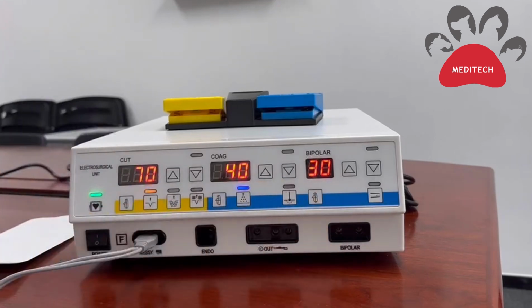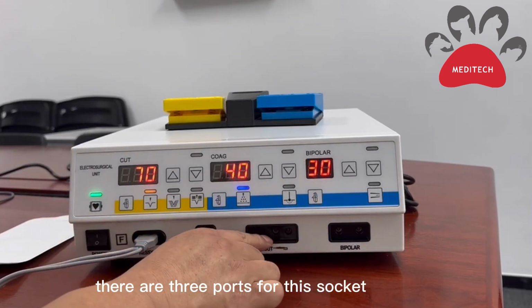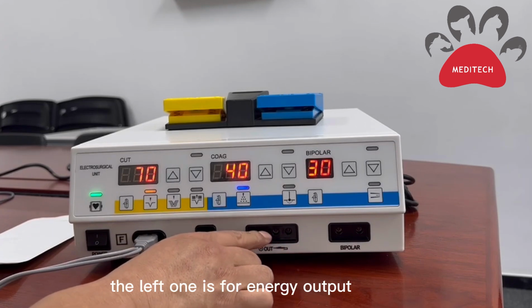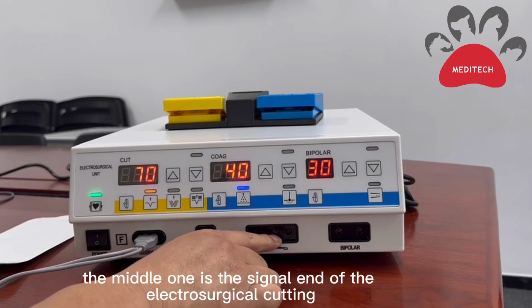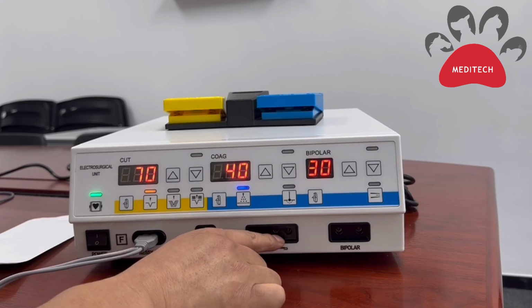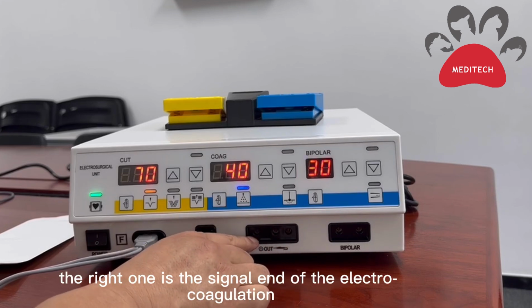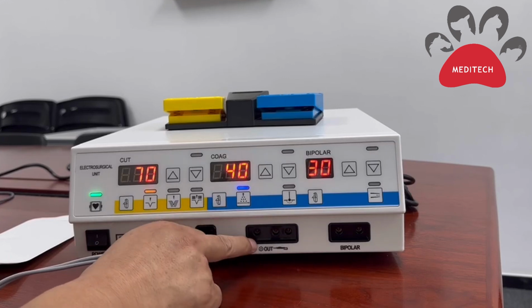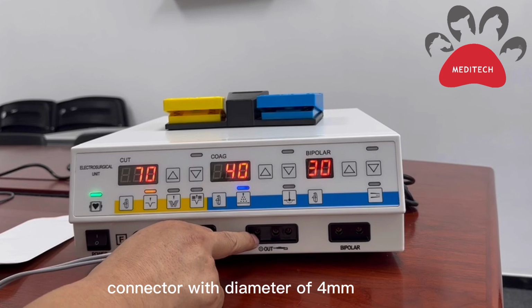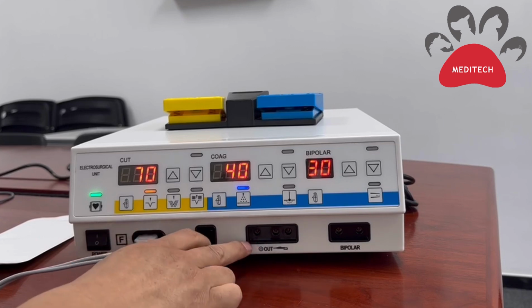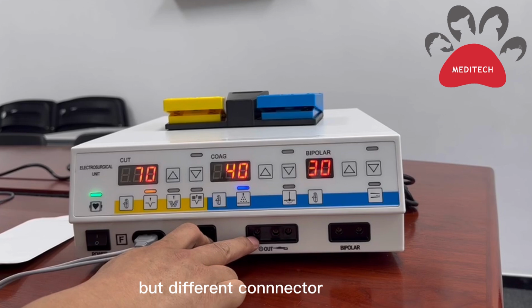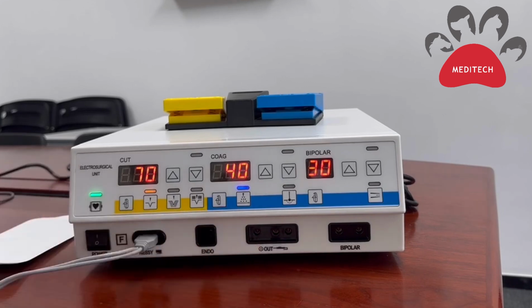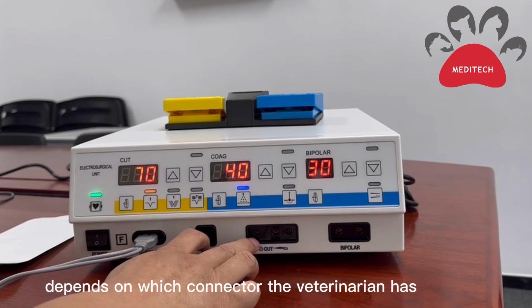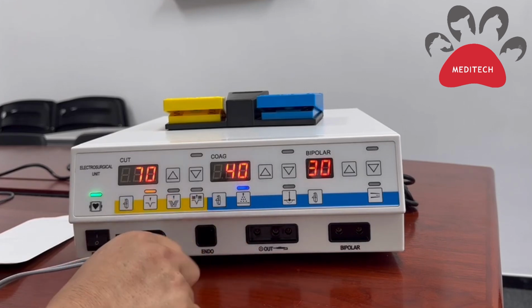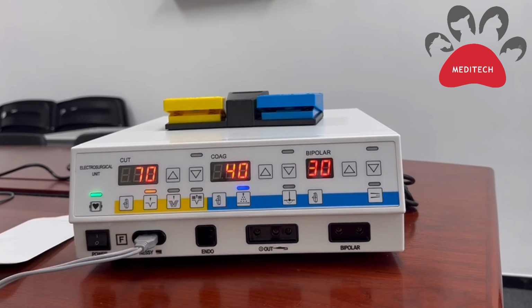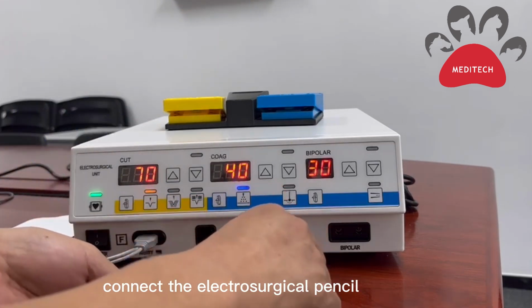There are 3 ports for this socket. The left one is for energy output. The middle one is the signal end of the electrosurgical cutting. The right one is the signal end of the electrocoagulation. The connector with diameter of 4 mm and the left one of 8 mm have the same function, but different connectors. It depends on which connector the veterinarian has. Both of the 2 ports can connect endoscope. Connect the electrosurgical pencil.